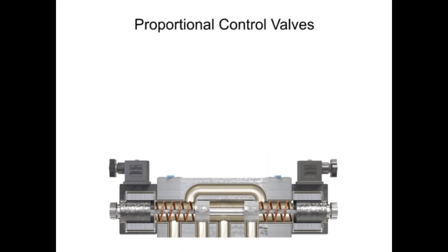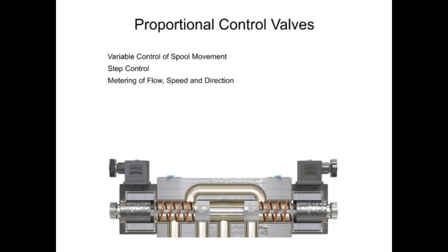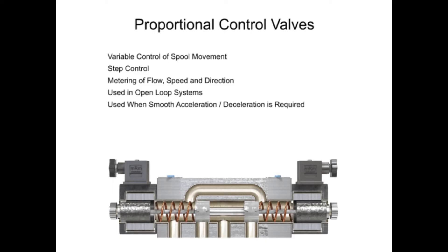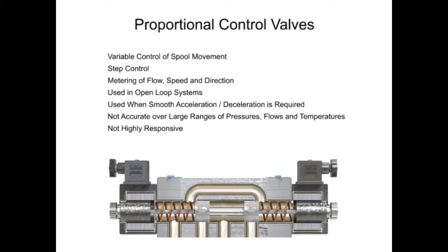Proportional control valves allow for variable control of spool movement, which allows more step control and metering of flow, speed, and direction. Most valves of this design are used in open-loop systems to smoothly accelerate and/or decelerate an actuator or cylinder. The proportional control valve allows for a simpler hydraulic circuit, but it is not accurate over a broad range of pressures, flows, and temperatures. Neither are they highly responsive. Proportional valves offer a variety of machine cycles, which can safely be operated at greater speeds, resulting in improved machine cycle times and production rates.